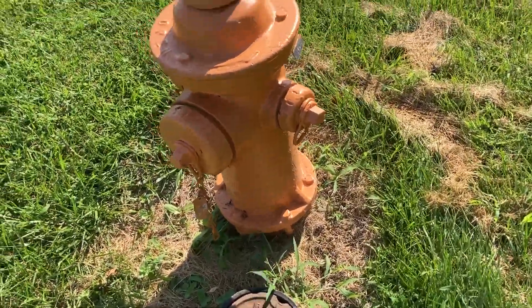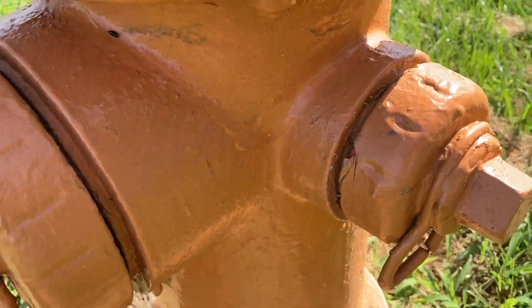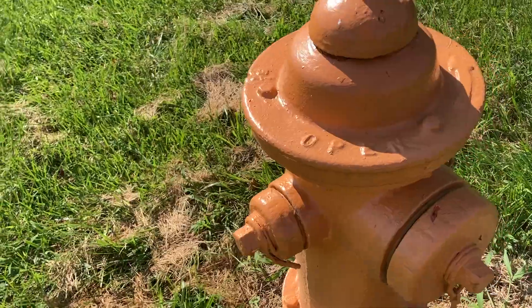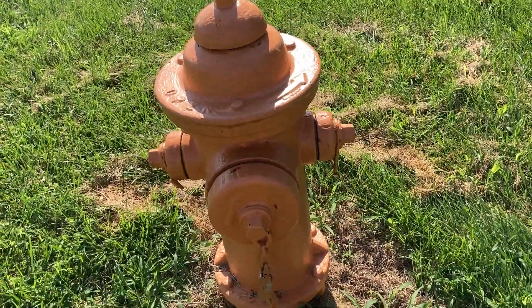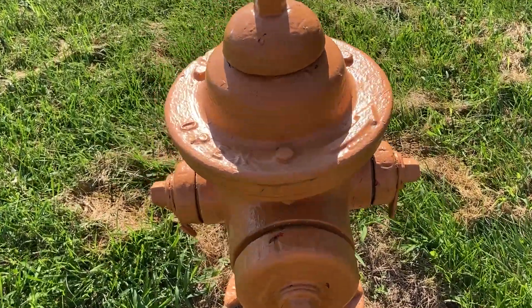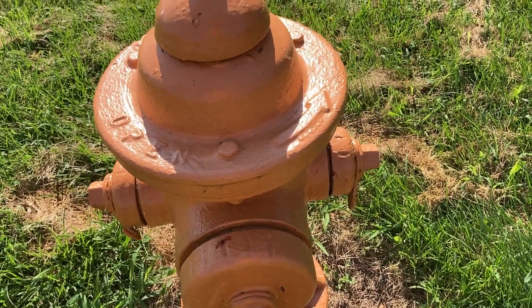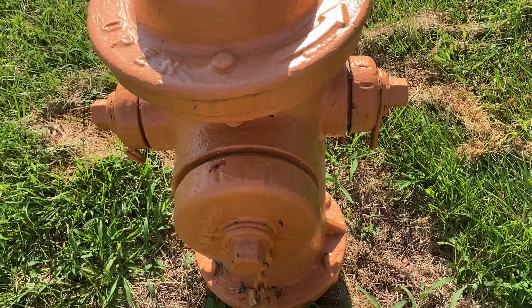The other issue on this hydrant, as you can see, are the chains. This is a McWane hydrant, and the chains have basically been taken off. Why put the chains on? The hydrant's almost 50 years old. The chains corroded so bad, they're galled from coats of paint. So the fire company or someone yanked them off. But the eyelets ought to be taken off with a bolt cutter and a pair of large channel locks.